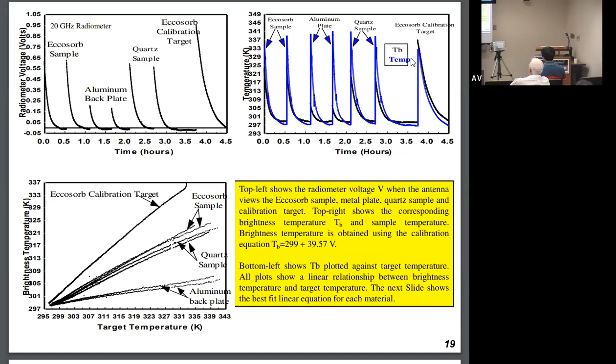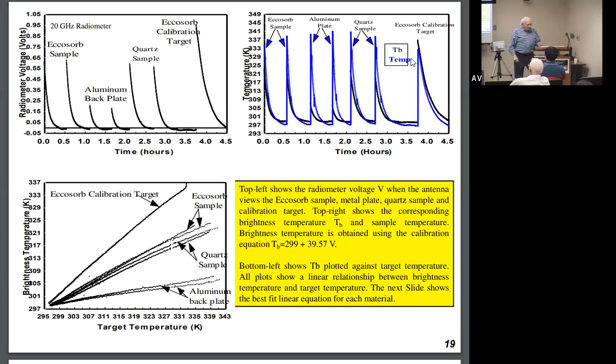Okay, got these three. Here's the Eccosorb. Here is the Eccosorb sample. I'll show you, it's a small piece. Here's the quartz, and here's the aluminum plate all by itself. When you look at that, and these are the slopes, you get these different slopes. Here's 0.658 for the Eccosorb sample. Here's 0.585 for the quartz sample. Here's the calibration target. Look how close it is to 1, which is what it should be. It should be identically 1.